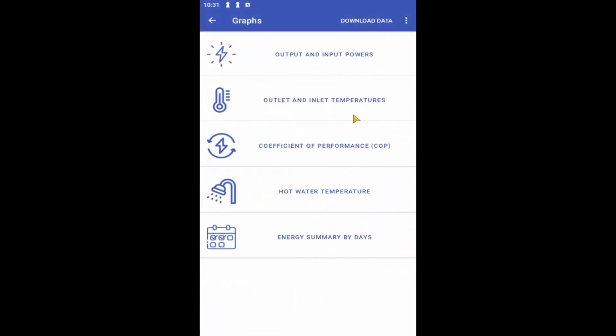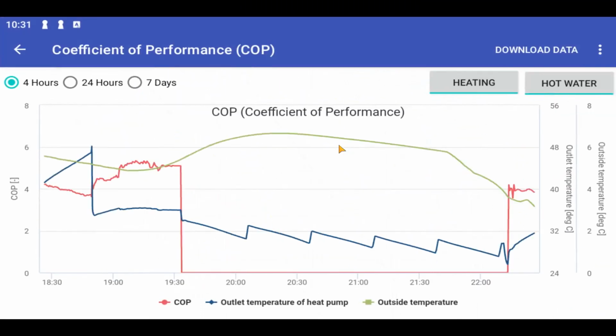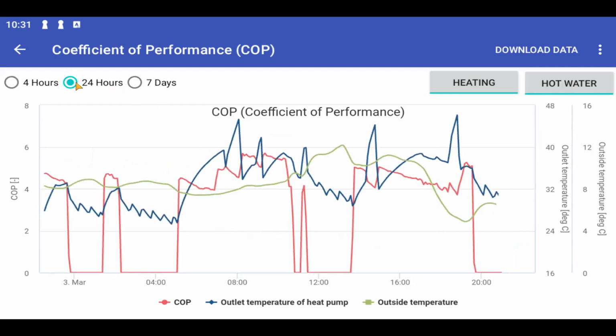Here, for example, is the progression of the heating factor, so you can see how I've been moving around for the last 4 hours. It was somewhere around 5.5, let's say. Over the last 24 hours, there will be similar values, even reaching around 5 at some point. The standard value is just over 4, which corresponds to the outdoor temperature, around 10 degrees. So, those are the basic functions in the graphs, and let's continue.